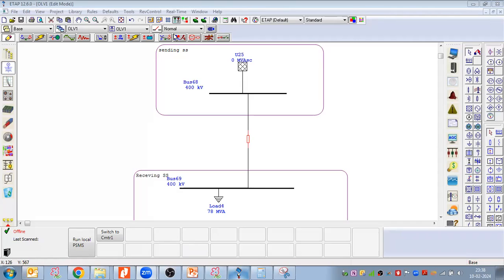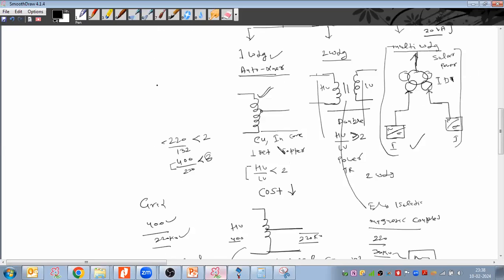Yes, a wave trap is a different equipment. It is designed to filter high frequency signals, so the wave trap stops high frequency signals and allows low frequency signals to pass. If you check the formula for the reactor, XL equals 2 pi F L, so when frequency is high, XL would be high. So this reactor is a kind of equipment which passes or which has higher impedance at higher frequency.